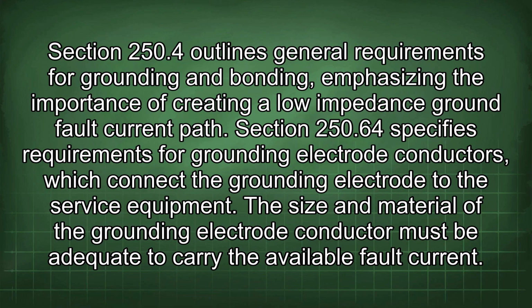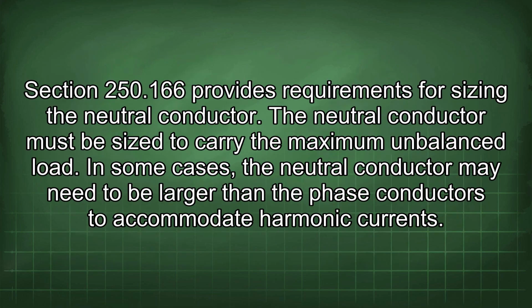path. Section 250.64 specifies requirements for grounding electrode conductors, which connect the grounding electrode to the service equipment. The size and material of the grounding electrode conductor must be adequate to carry the available fault current. Section 250.166 provides requirements for sizing the neutral conductor.